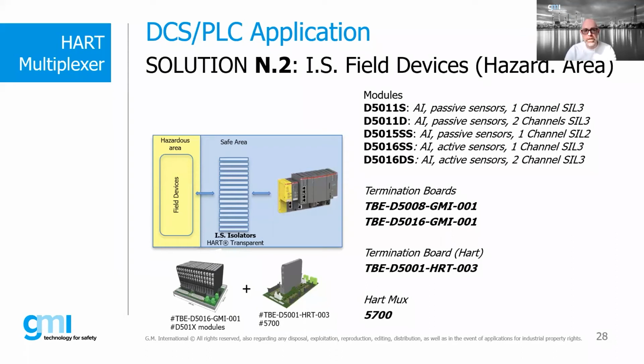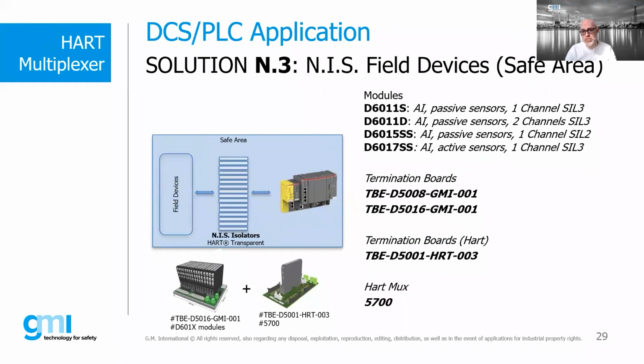A third solution has been tested, very similar to the previous one, but in this case we are going to manage applications that are not intrinsically safe. Here the isolation of the field signal is provided through isolators. As we can see from the slide, the listed models related to the device that must now perform the isolation of the field sensor toward the PLC system change code, but the system termination board models and the models for HART integration remain the same as in the previous type of application.